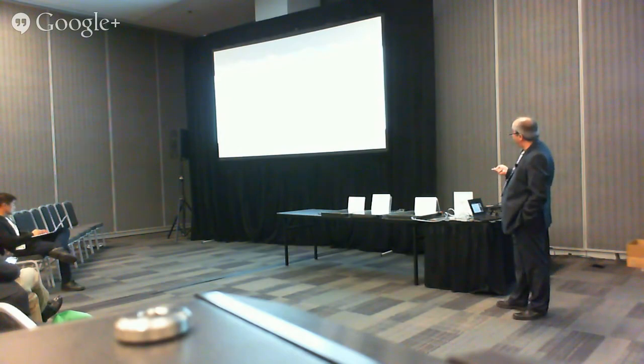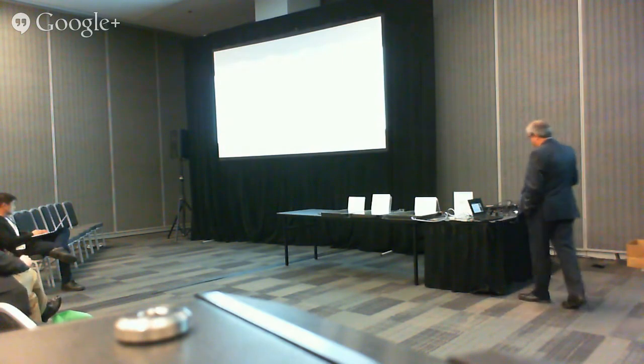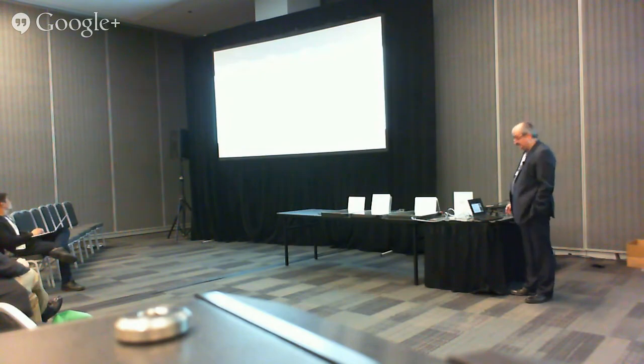Here is, for example, the reliability test on this device. You can see that we have the highly accelerated aging tests going out for quite a while now, past 10,000 hours, which basically, with that kind of acceleration, means the device life is proven for well over 7-8 years already.